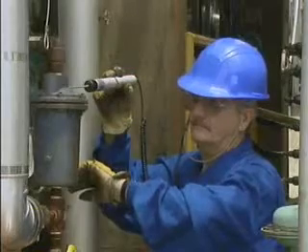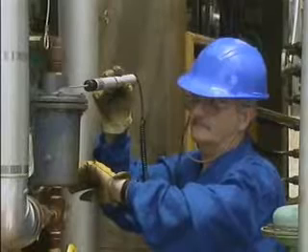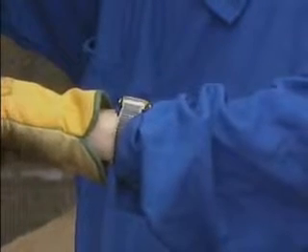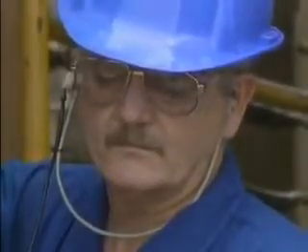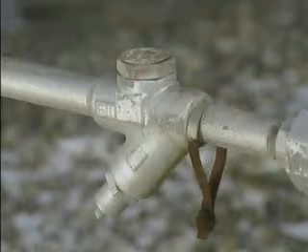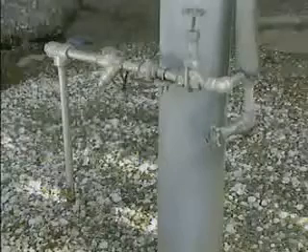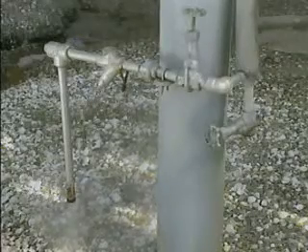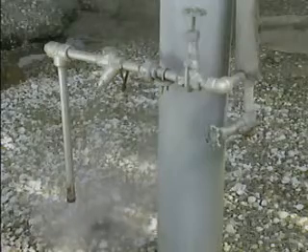If the discharge is intermittent, the cycle rate should be timed, and the time should be compared with the cycle time that your facility or the manufacturer lists as normal for that particular trap. Different traps have different discharge cycle rates. Disc traps, for example, are designed to discharge intermittently, so a continuous discharge could indicate serious problems.